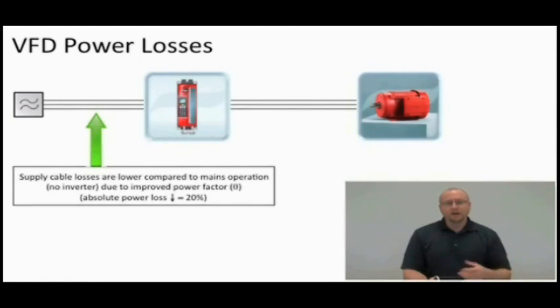There's going to be a huge phase angle there, a big power factor, and you're going to lose some energy there to reactive power. With an inverter, it's like an automatic power factor correction. It actually has a slightly leading power factor, and you can save energy. You can actually save up to 20% of your losses on that cable in that portion of the system. So that's actually a gain that you automatically get by putting an inverter in. It does not outweigh the other losses, but there are still things that we can do to save energy.